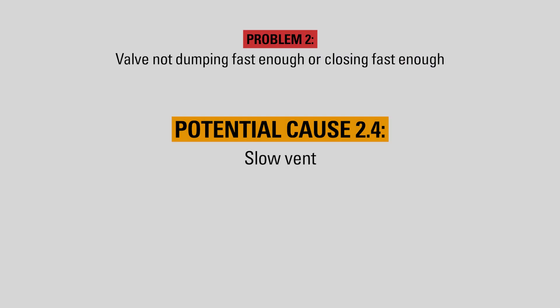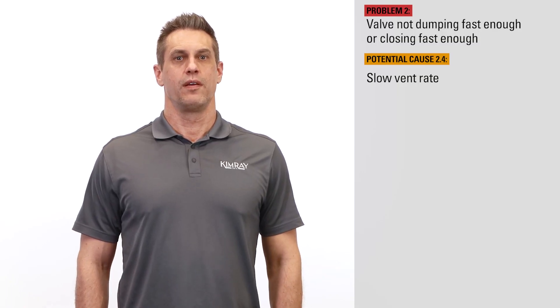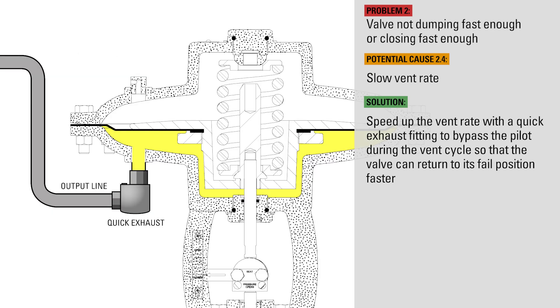In some applications, the vent rate through the Gen 3 pilot may just be less than what you need. If you want to speed up the vent rate, Kimray offers a quick exhaust fitting, which bypasses the pilot during the vent cycle so the valve can return to its failed position faster.